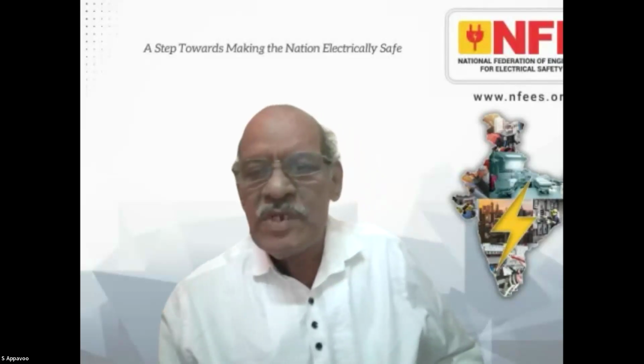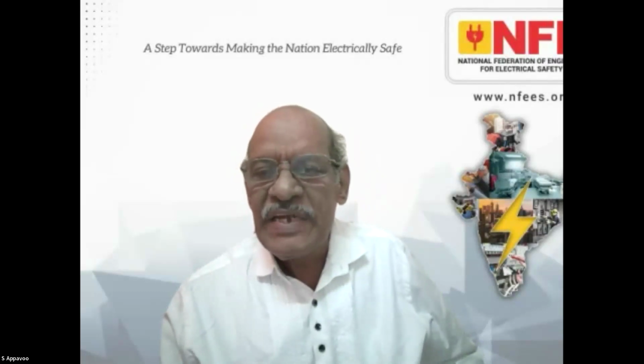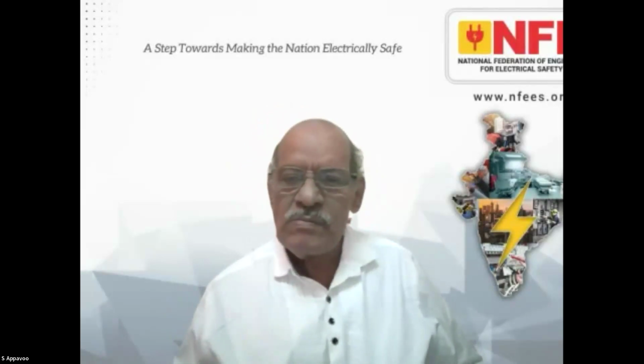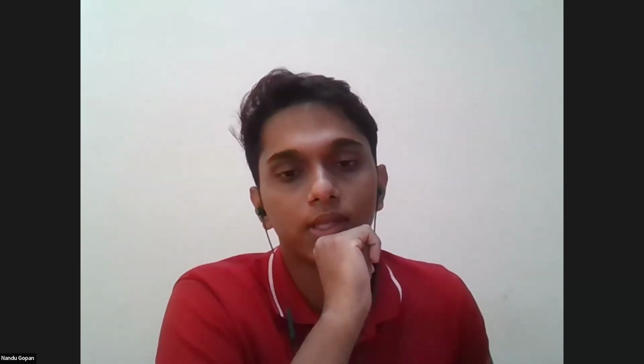So another question is from Mr. Balu. Is SPD require backup fuse? Yes, you are supposed to use it with a backup fuse, because there is a huge probability of SPD failing in case of over voltage. And the problem with SPD is, if it has failed due to over voltage, then it will create a short circuit. And in case the upstream MCB or MCCB, whatever the protective device is, doesn't disconnect, then you will face a huge serious problem. So you are supposed to use it with a backup fuse.